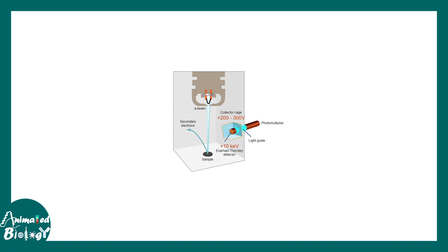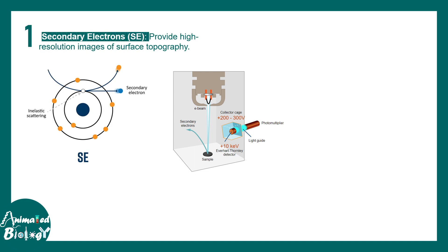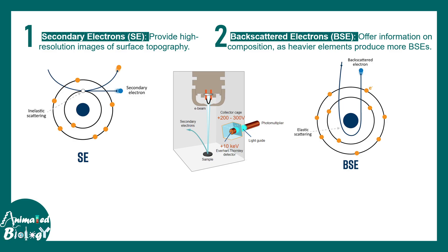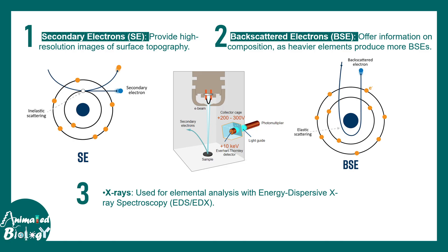There are three types of electrons generated. First, secondary electrons are produced when the electron beam kicks out electrons from the outer orbit of atoms in the sample — detected by secondary electron detectors. Second, backscattered electrons are those that penetrate an atom but undergo elastic scattering and move in the backward direction — they offer information about composition and provide greater image contrast. Third, X-rays are used for elemental analysis via energy dispersive X-ray spectroscopy, though this is beyond the scope of this video.